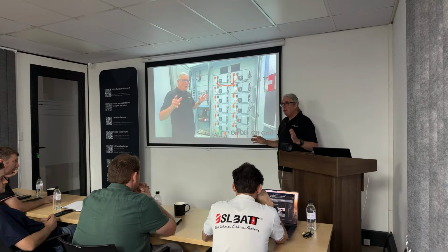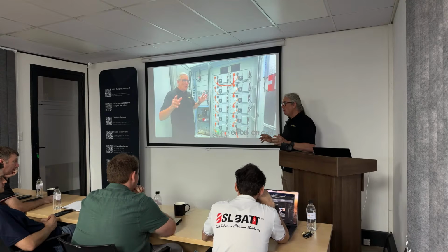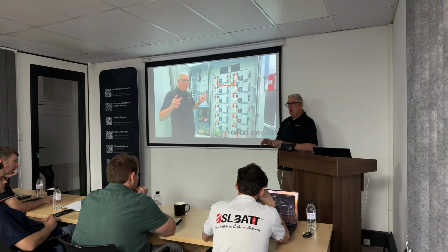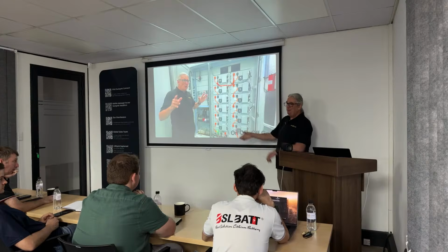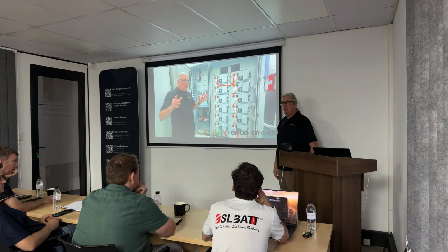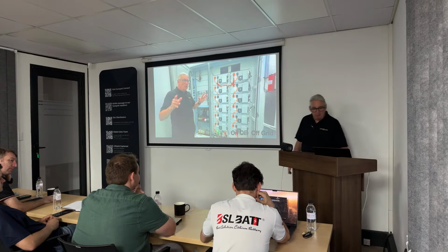By doing it the way we do it here on the power hubs, it can't happen. It works independently. So you've got a nice noisy generator that can't cause issues - we can take whatever power. If the generator frequency is running at 47 hertz, it doesn't matter. It will still output DC, and it will go straight DC onto the line. So that's an important feature - it's a really, really important feature.